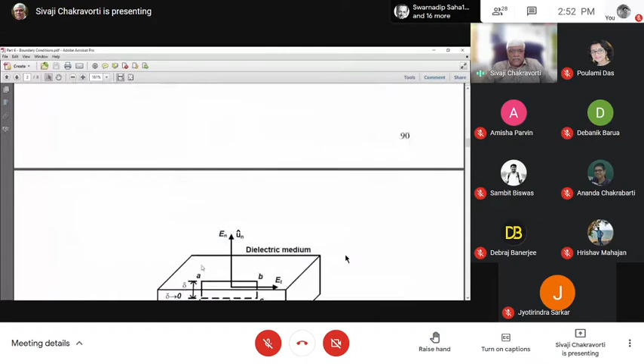So what is the field intensity just off the conductor? Yes, that is quite obvious, that Et becomes zero on the surface. So just off the conductor surface, dN is equal to sigma. So equation 6.10 says that En will be dN by epsilon, so sigma by epsilon, or sigma by epsilon 0. So this is the field intensity just off the conductor surface, and that is why we always say that if the surface charge density is high, the field intensity just off the surface becomes high. And that is the explanation of why corona takes place: if there is a sharp corner on the electrode surface, then naturally the area decreases, charge density increases, field intensity increases, and corona takes place. This is the very straightforward explanation of corona occurring if there is a sharp corner or sharp point on the conductor surface.